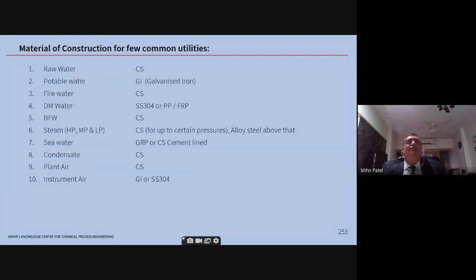Then materials of construction for a few common utilities I am giving here. Now here you see raw water is normally carbon steel. Potable water is GI, galvanized iron, which does not corrode. But the only thing is, potable water GI has a drawback because you cannot weld GI. So you have to have union couplings in the middle.